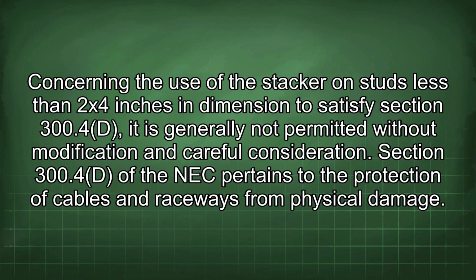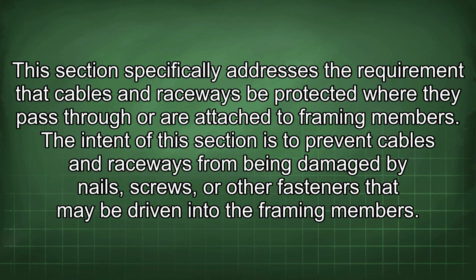Concerning the use of the stacker on studs less than 2x4 inches in dimension to satisfy Section 300.4(D), it is generally not permitted without modification and careful consideration. Section 300.4(D) of the NEC pertains to the protection of cables and raceways from physical damage. This section specifically addresses the requirement that cables and raceways be protected where they pass through or are attached to framing members.